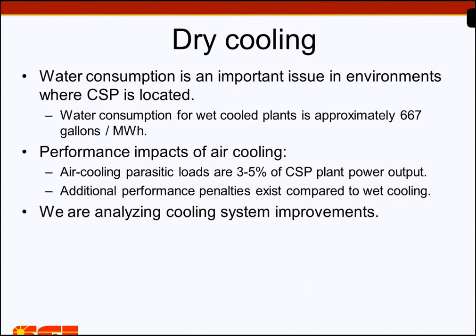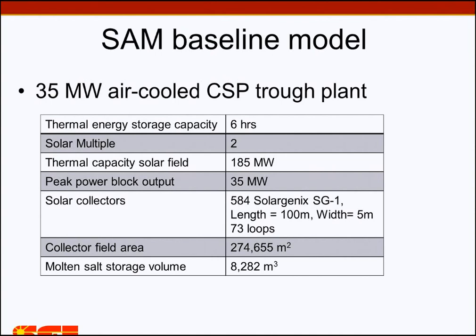Because of this, most CSP plants are moving towards dry cooling systems. That's good for water use, but there are some performance impacts. First, there are parasitic loads for air cooling — because you're pushing air instead of pumping water, parasitic loads are somewhere around three to five percent of power output, whereas wet cooling would be much lower, maybe around one percent. Additionally, there are performance penalties because you can't achieve as cold condensing temperatures with dry cooling as with wet cooling.